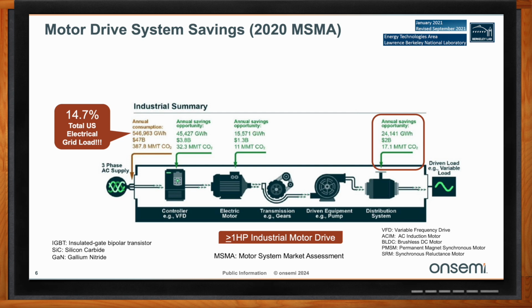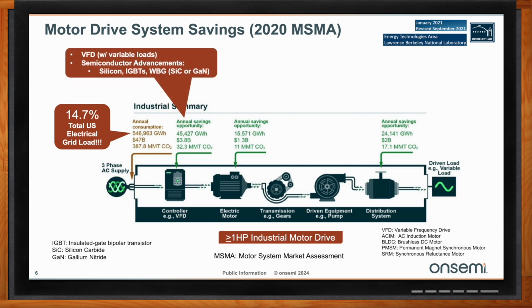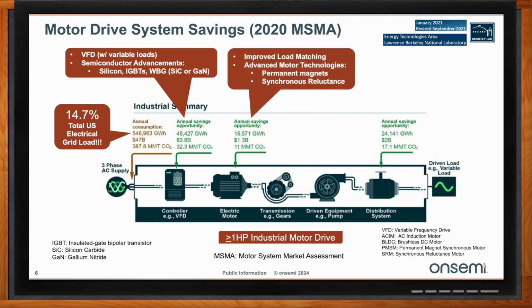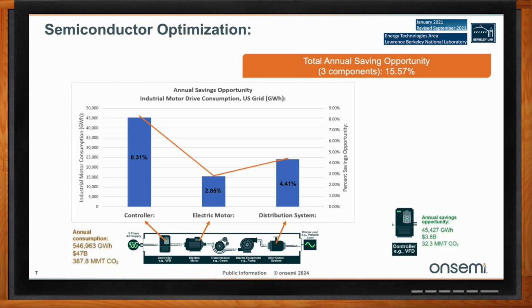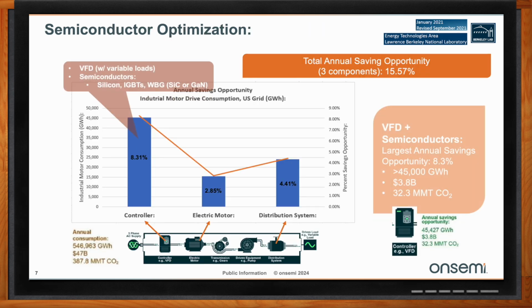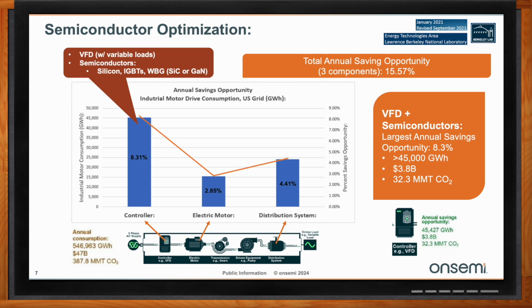Basically, what's inside that controller, or the VFD, is a bunch of semiconductors, namely silicon IGBTs, and wide bandgap, which includes silicon carbide or gallium nitride switches. If you look at the motor, that's really improving the load matching as well as advanced motor technologies like permanent magnets or synchronous reluctance. And then finally, the third savings in the distribution system is periodic maintenance. If you crunch these numbers in an Excel spreadsheet, you can see that the controller amounts to an 8.31% savings in annual consumption. The electric motor is 2.85%, and the distribution system is 4.41%.